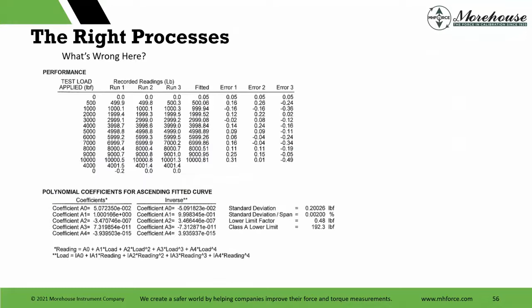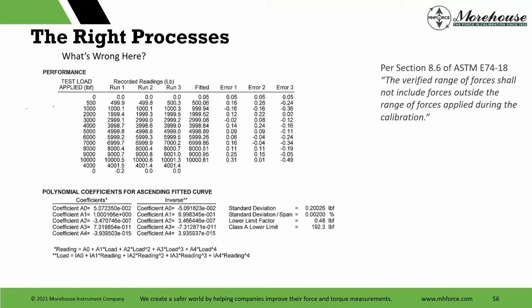This is another process. We see this a lot. ASTM, the standard that's being followed. The verified range of forces shall not include forces outside the range of calibration. So 0 is not a force point, right? It's not in the range of calibration. If you look in the ASTM standard, there's specific guidance that says the first force point shall not be less than 400 or 2,000 times the resolution. It also says 0 is not acceptable. So right here, the first force point is 500 pounds of force.